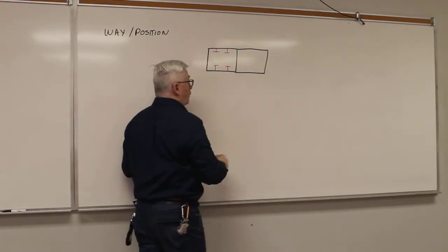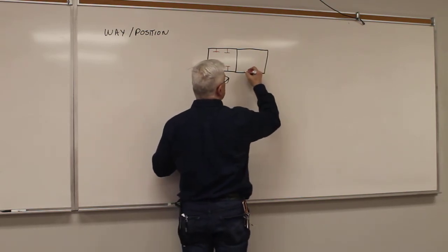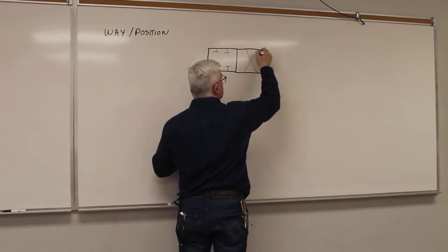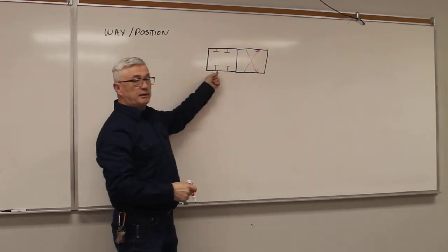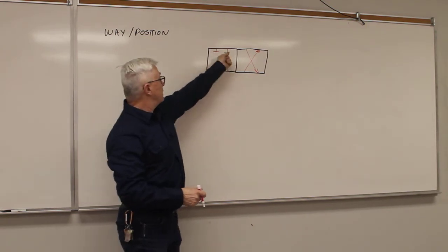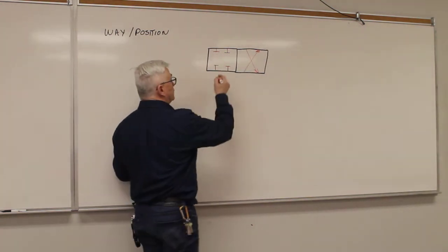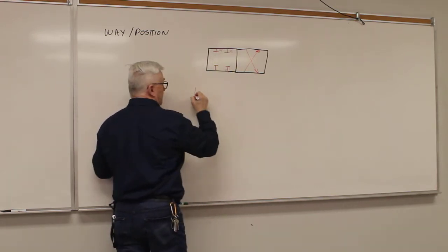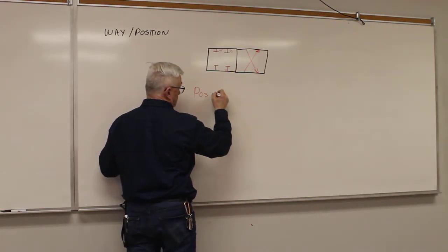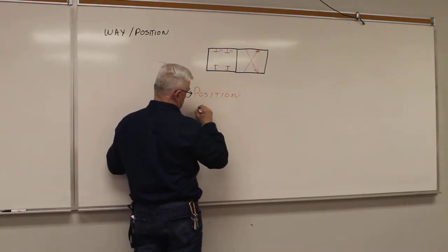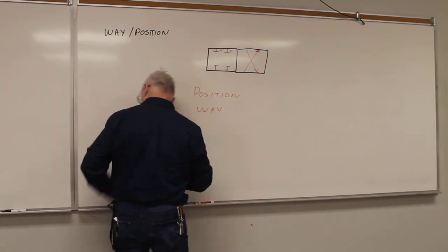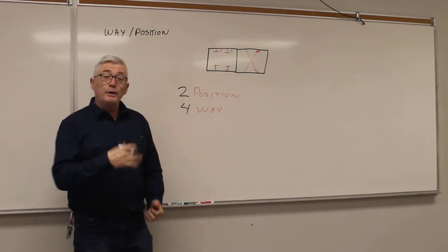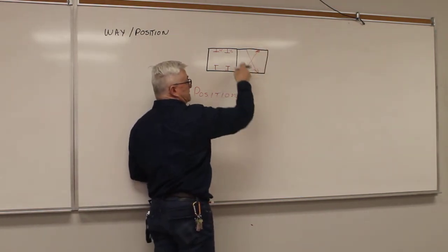All right. Now, what we would have maybe in the next one is one where we simply allow the fluid to cross in direction. So when it's in this position, which is normally the home position, there's no oil can flow. But this one, we would count them out, 1, 2, 3, 4. So this would be a two-position, four-way valve. We don't worry about the other box and count them as 5, 6, 7, 8.